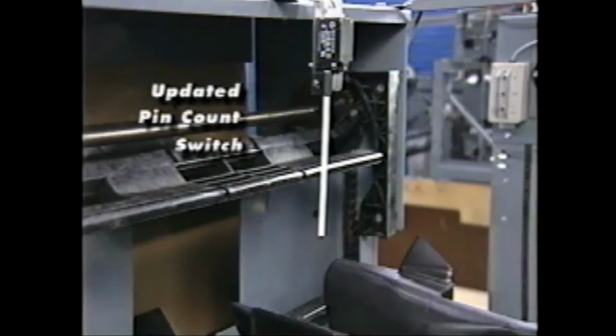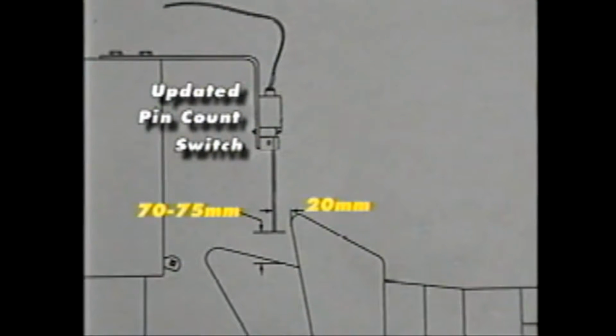The bottom of the actuator on this version of the pin count switch only needs to be positioned 20mm away from the imaginary line and 70 to 75mm above the top of the wedge. Please refer to the service manual for further details.